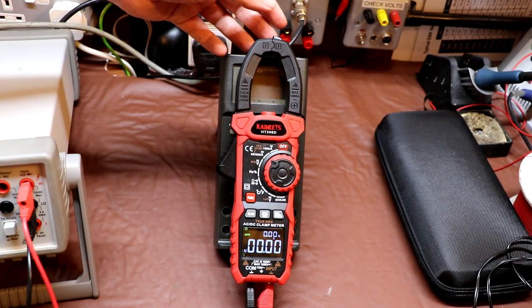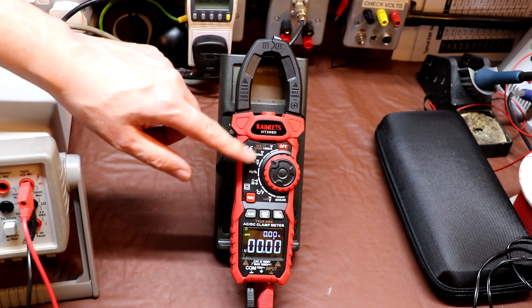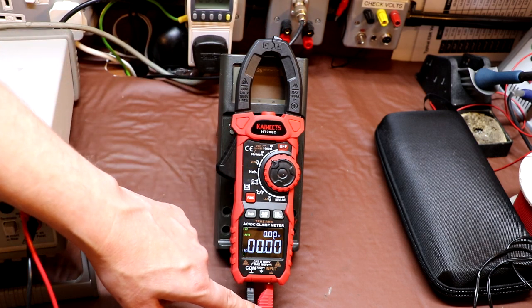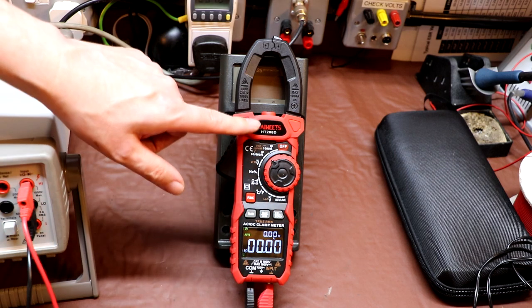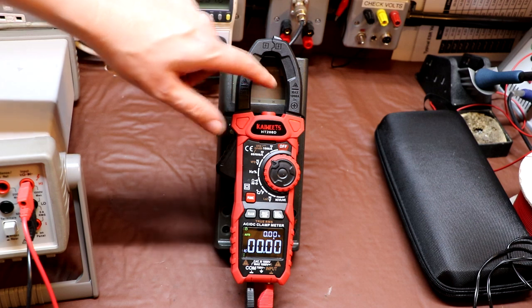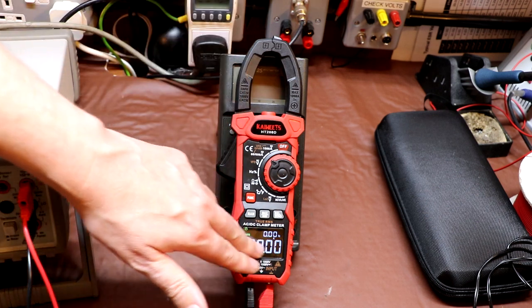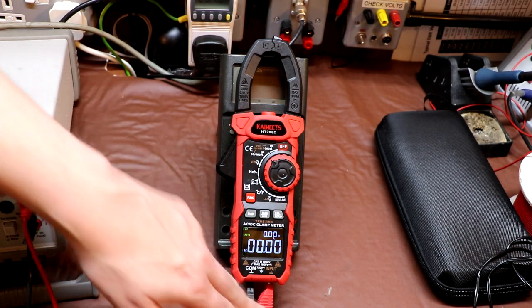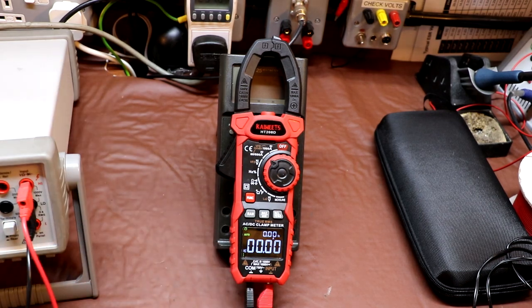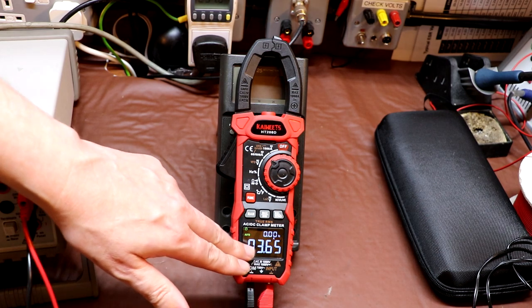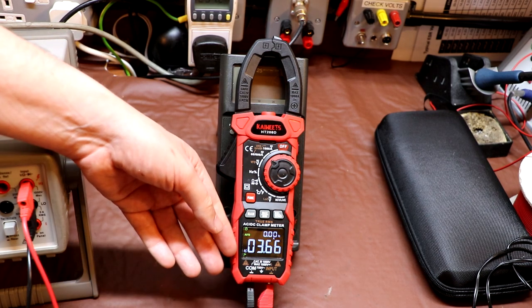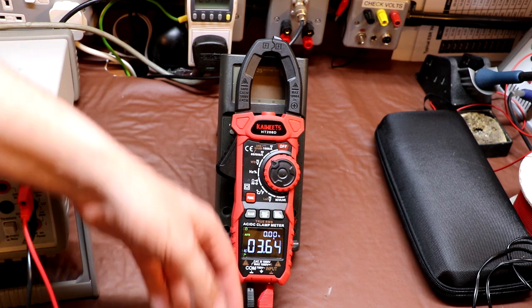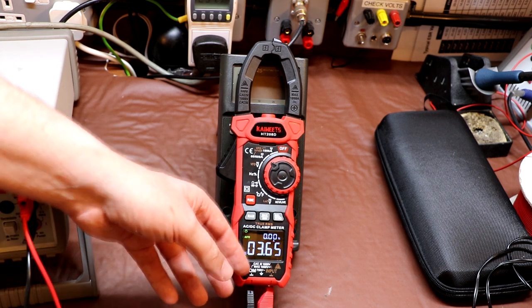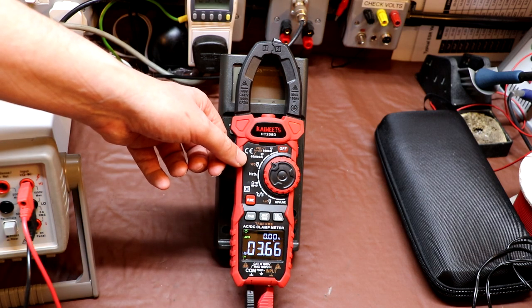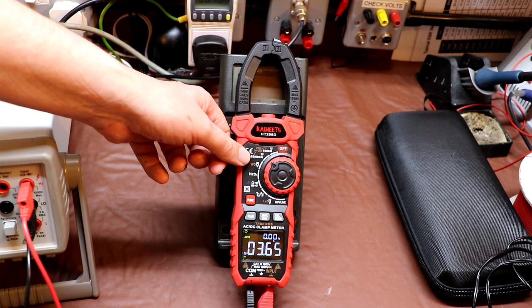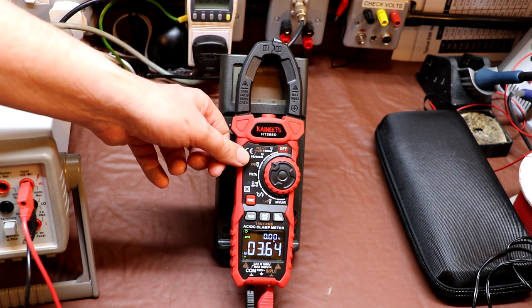But a more significant problem that I found with the KAIWEETS meter is that when we're in the current range, if we have any connections made to the meter for the voltage input, it actually affects the current range. At the moment you can see that we don't have a wire going through the jaws and it's showing 0, 0, 0. That's what we'd expect. But if I just turn on a voltage supply to these terminals, you can see that the meter starts indicating 3.6 amps. We shouldn't be seeing a reading here, and if by error you left the meter connected to a source of voltage, it would clearly affect the current measurement. So that affects my confidence in the meter's ability, and that could perhaps lead to an unsafe situation.